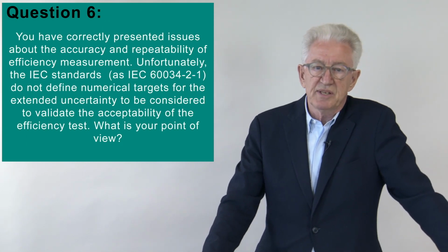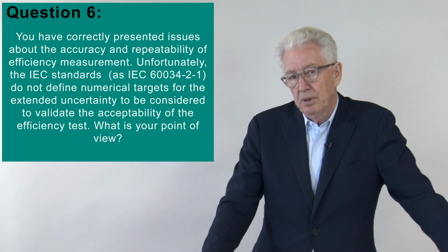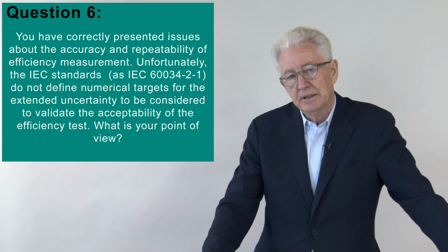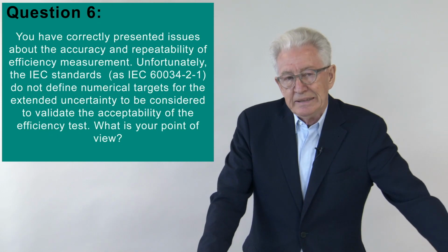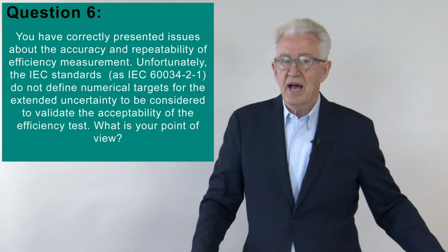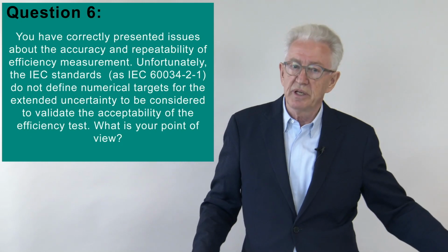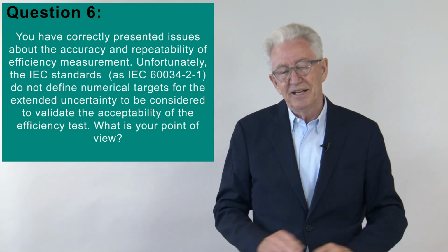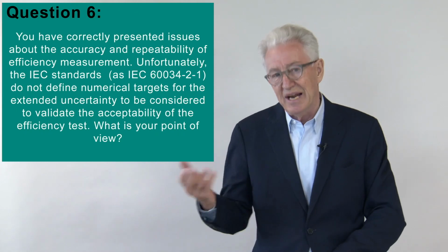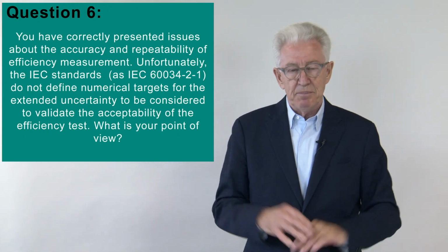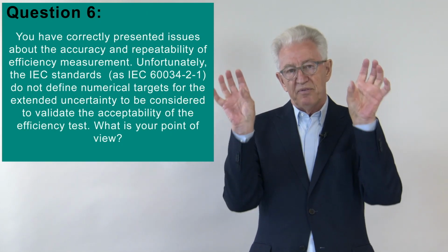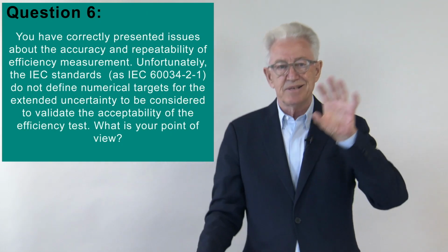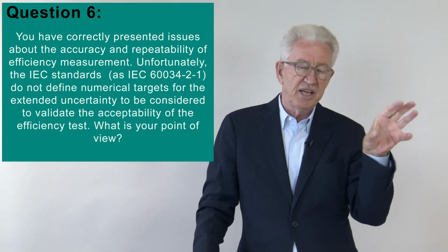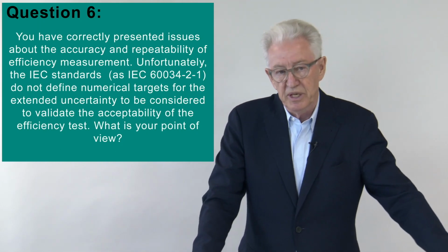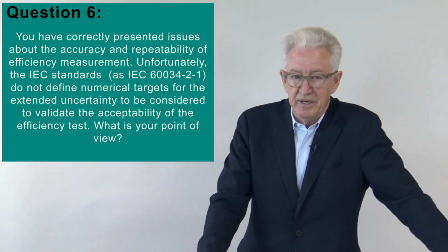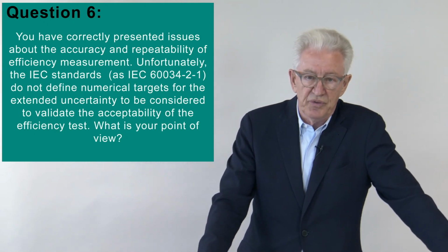Usually the torque meter is the most sensitive element, and there are people who can handle that. Many university labs do it, usually with highly efficient equipment, but then they have students running a lab test who can ruin the accuracy of the torque meter, requiring it to be recalibrated, which is a lengthy procedure. This means the performance quality of manufacturing and the quality of the instruments and their operation have to be put together to get a clear uncertainty calculation for the whole thing.